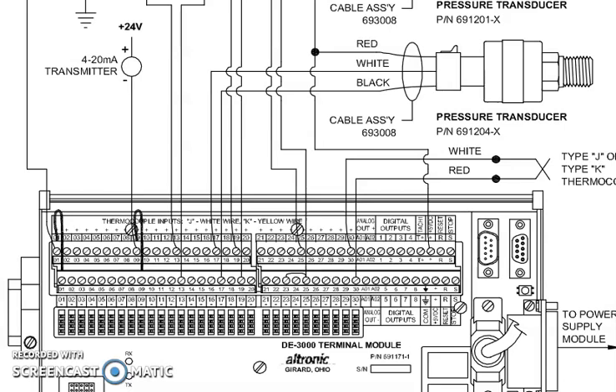So let's look at the diagram first. And here we have a transmitter. It's receiving 24 volt positive on one side. And this is a typical 2-wire 4 to 20 milliamp pressure transducer. There's a lot of different pressure transducers on the market that wire different ways. Some of them receive 24 volt positive and negative supply sources to power them. Maybe they have a little LED crystal display on the pressure transducer, and then they may have two separate wires that come out. Now those wire up a little bit different, but really pretty much the same way.